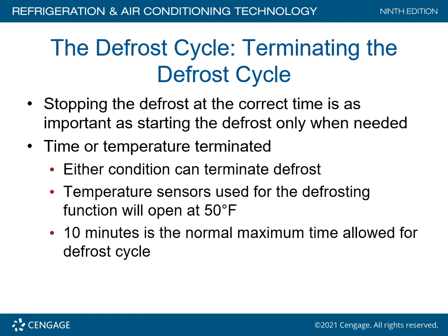Pardon me. Defrost cycle, terminating the defrost cycle. Stopping the defrost at the correct time is as important as starting the defrost only when needed. Demand defrost, time and/or temperature terminated. So either the timer, electronic, or the temperature sensor could terminate defrost. Either condition will terminate. Temperature sensors used for the defrosting function will open at 50 degrees Fahrenheit. 10 minutes is the normal maximum time allowed for defrost to take place.